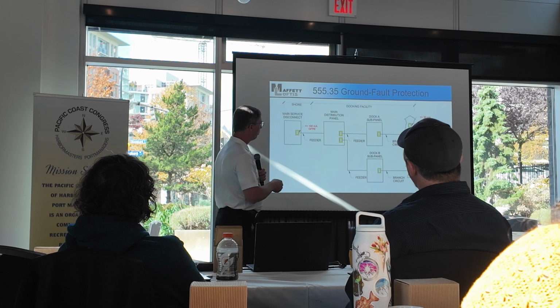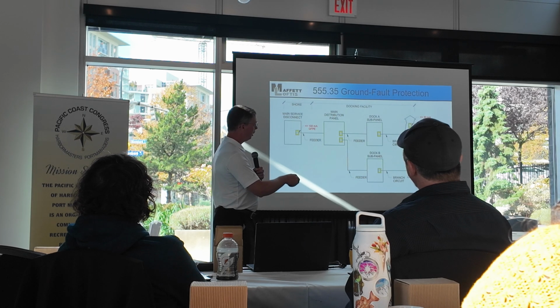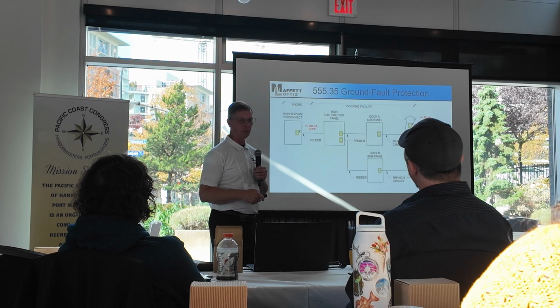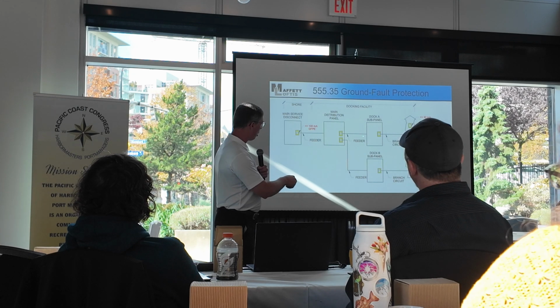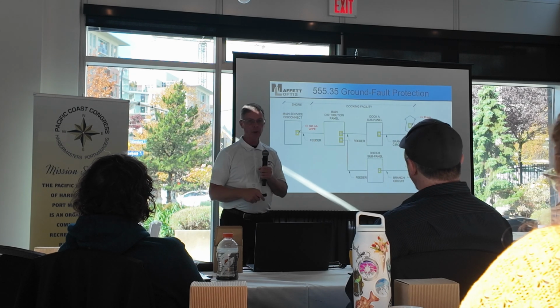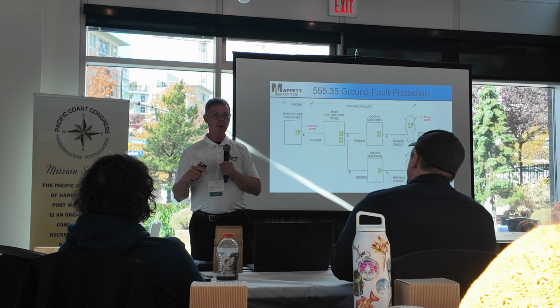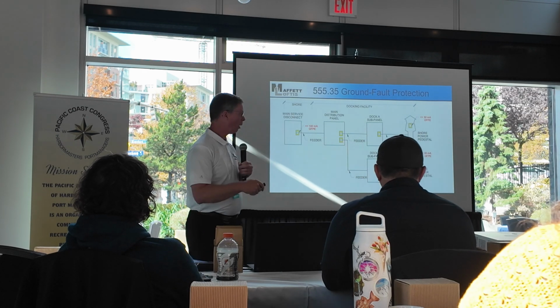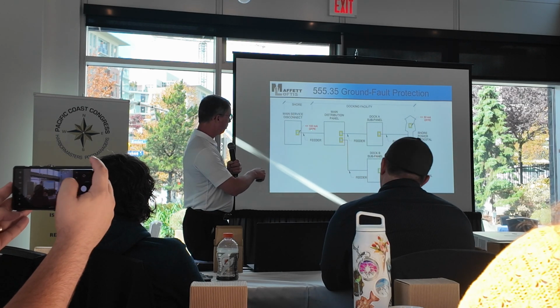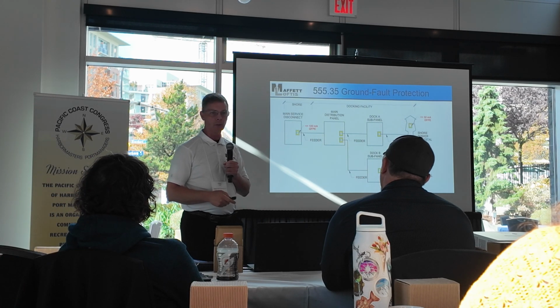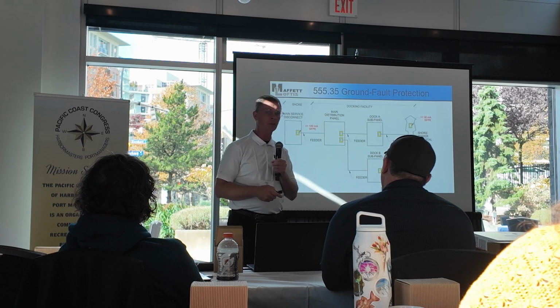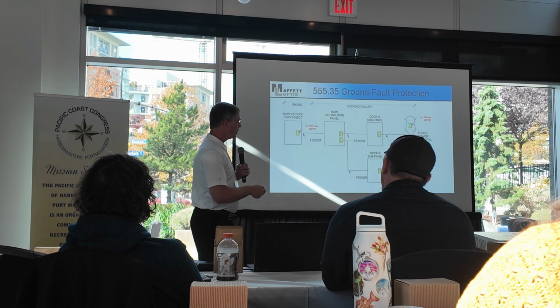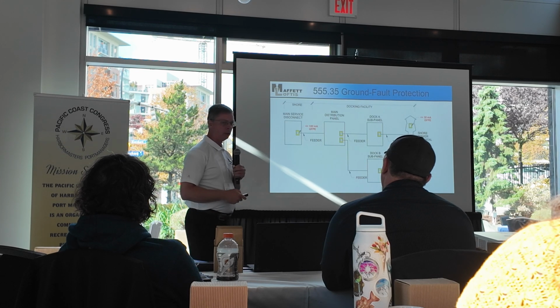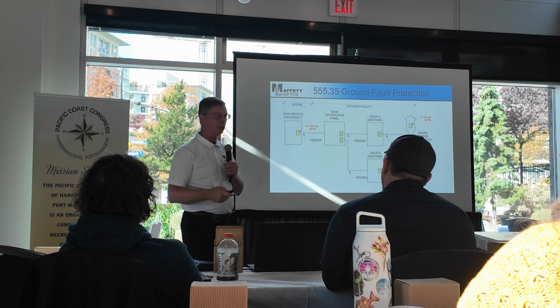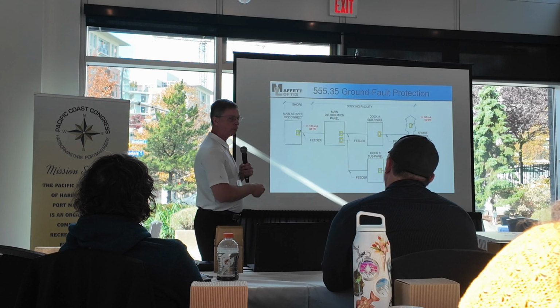Under 555.35, it requires 30 milliamps on the shore power and 100 milliamps to protect all the feeders and branch circuits. What's more strict about the Canadian code is that it requires 30 milliamps up there, and if you have 30 milliamps there, you don't have to have anything else downstream. Right? That's under rule number 78 of the CEC. So this is a little bit more lenient compared to the Canadian code, but it's still an issue because you don't want the main to trip, right?